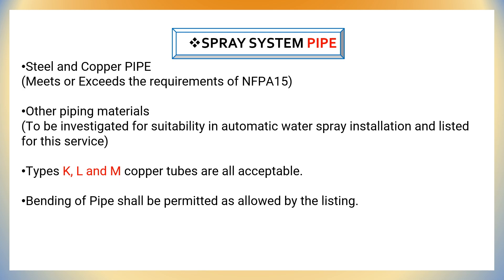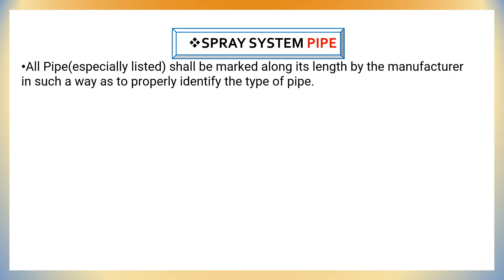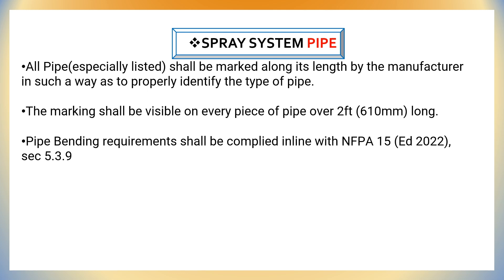Pipe bending shall be permitted as allowed by the listing. In most cases we are going to bend the pipe as per project site requirements. Pressure limitations and wall thickness for steel pipe shall be in accordance with NFPA 15 clause 5.3.5. All pipes, including specially listed pipe, shall be marked along their length by the manufacturer, and the marking shall be visible on every piece of pipe over 2 feet long. Pipe bending requirements shall be in compliance with section 5.3.9 of NFPA 15 edition 2022.